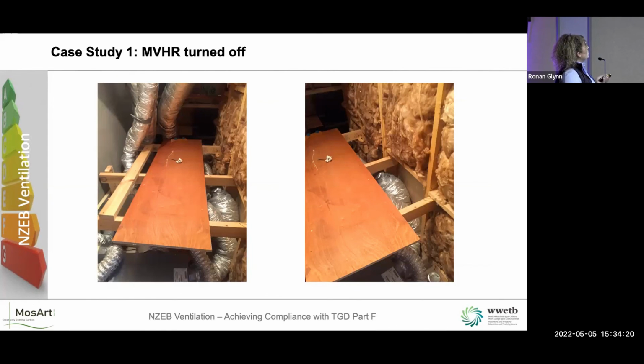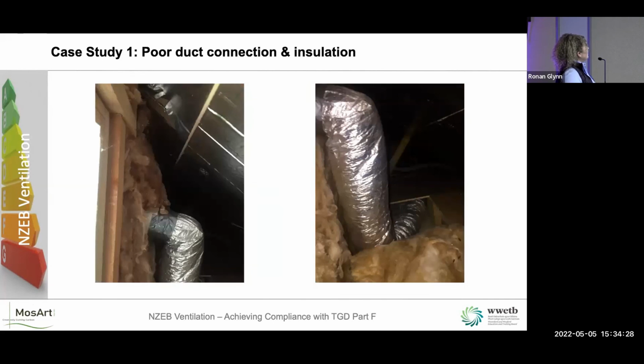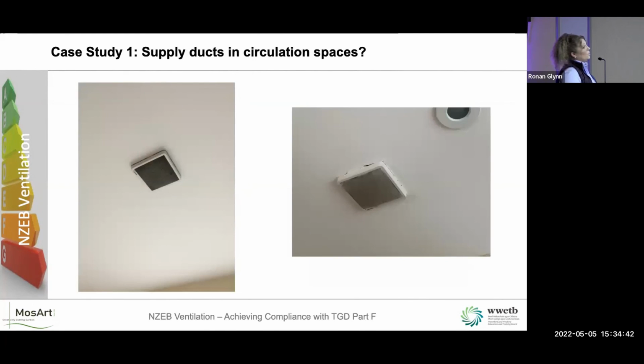So what happened was it was so poorly installed, you can see the runs of duct and they're all bunched up there all over the place. There was no connection here, it was just duct tape holding the duct onto the hole in the wall, the outlet. Hard bends on it, okay, lots of flexible ducting. So the unit failed. It was eventually turned off. They had no supply in the bedrooms. They had 2 out on the landing though, so I don't know what that was about. And also the filters were on the outside of the diffuser and they were black dirty as well. So these guys were sent in to inspect it to see what they could do to improve the air quality in the house. So they had some job ahead of them.